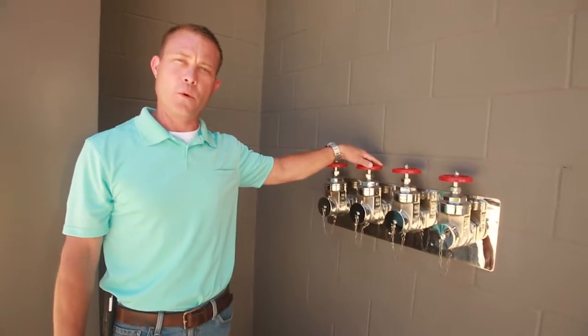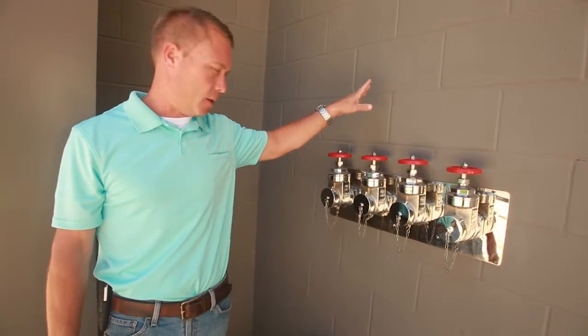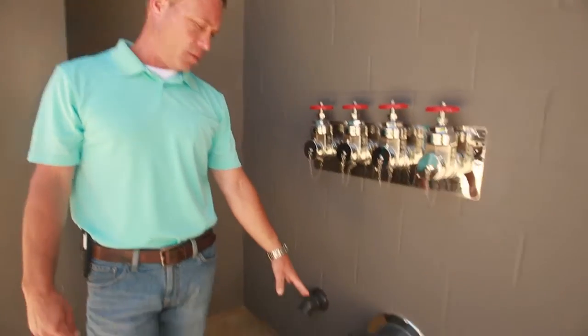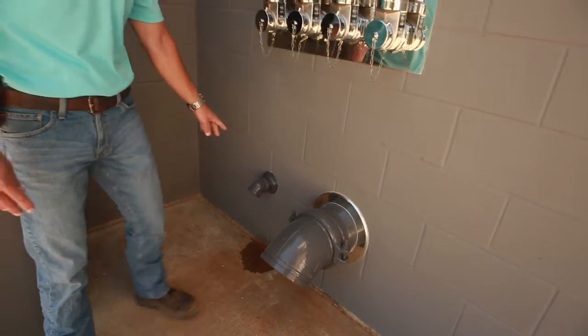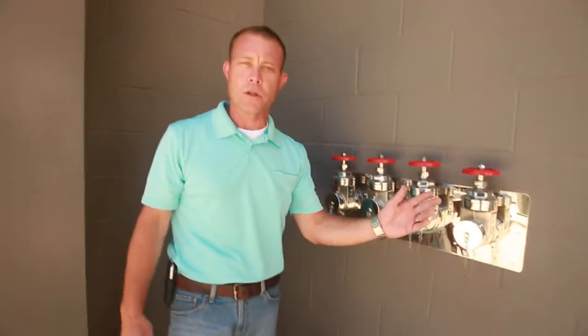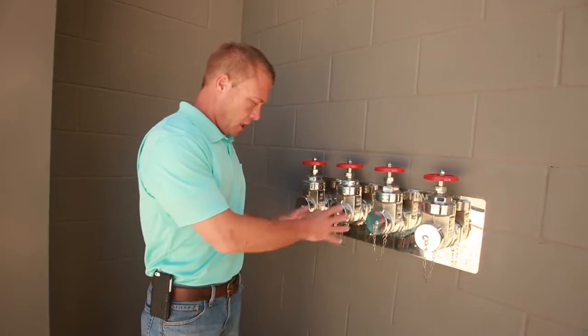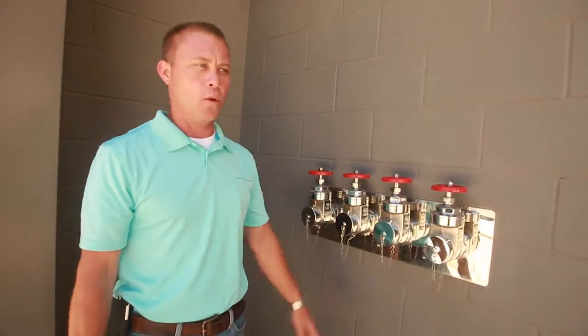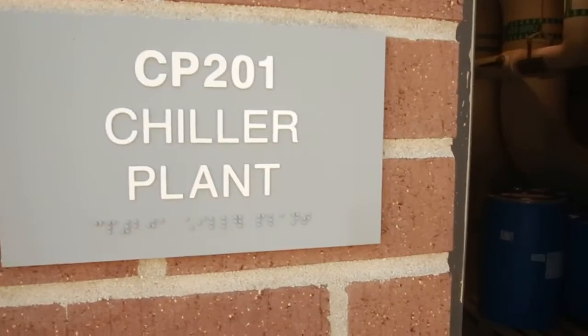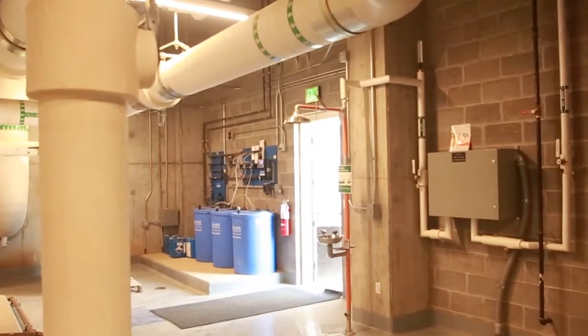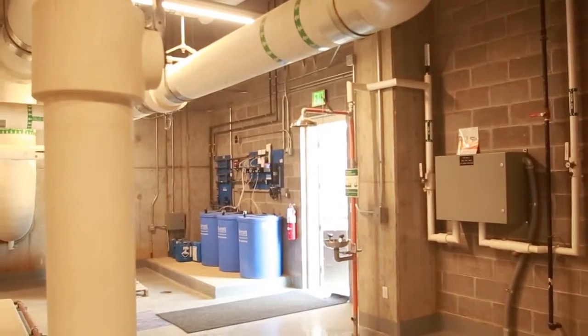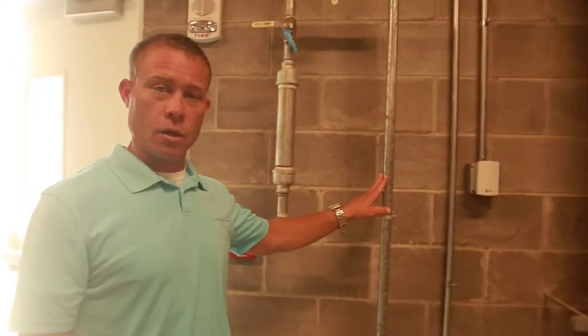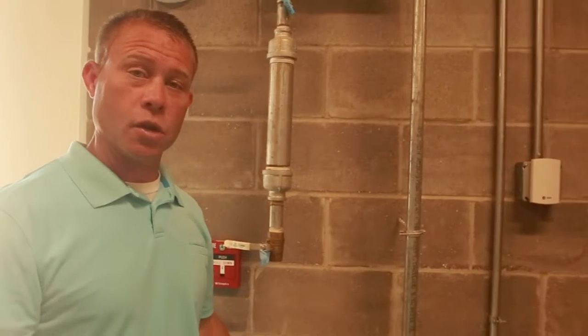This was the test header for both pumps. Again, they're connected in there, and we just talked about this is your relief valve piping, and this is your main drain that earlier we talked about all the risers connecting to, and that's all on the north wall of the CEP. To test the flow switch for the wet pipe sprinkler system, you need to open the valve located in the chiller plant labeled inspector's test, which discharges out of the north wall of the CEP. The dry pipe valve is equipped with an alarm pressure switch. For testing, the inspector test is located in the generator room and is discharged on the east side of the wall.